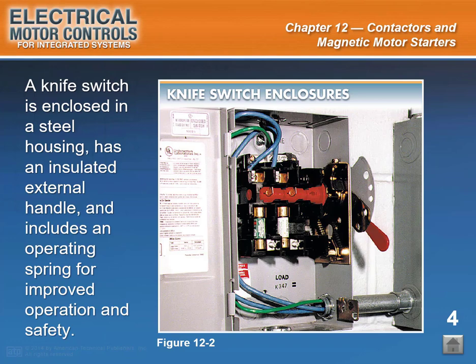A knife switch is enclosed in a steel housing, has an insulated external handle, and includes an operating spring for improved operation and safety. See Figure 12-2. As industry demanded more electric motors, improvements were made to knife switches to make them more acceptable as control devices. First, the knife switch was enclosed in a steel housing to protect the switch from external forces and from emitting sparks. An insulated external handle was added to protect the operator.